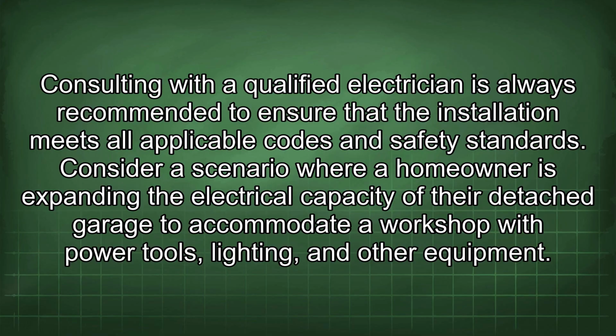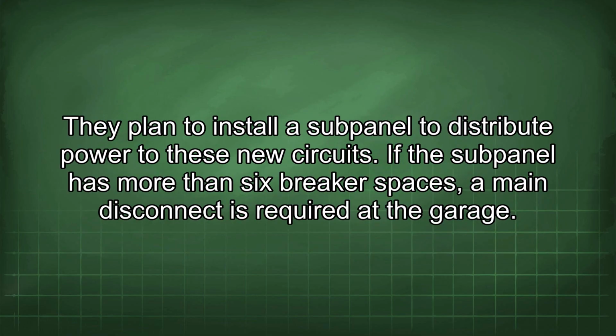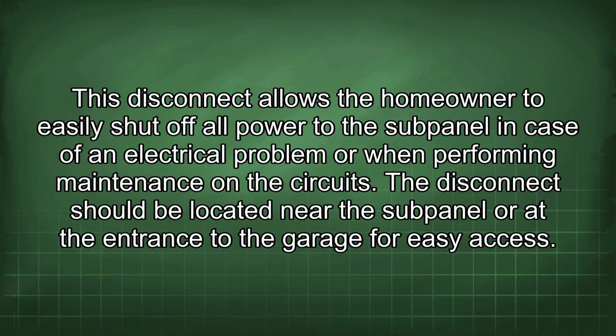Consider a scenario where a homeowner is expanding the electrical capacity of their detached garage to accommodate a workshop with power tools, lighting, and other equipment. They plan to install a subpanel to distribute power to these new circuits. If the subpanel has more than 6 breaker spaces, a main disconnect is required at the garage. This disconnect allows the homeowner to easily shut off all power to the subpanel in case of an electrical problem or when performing maintenance on the circuits.